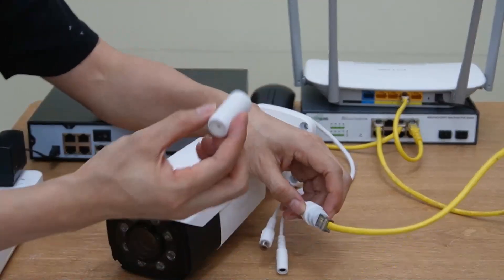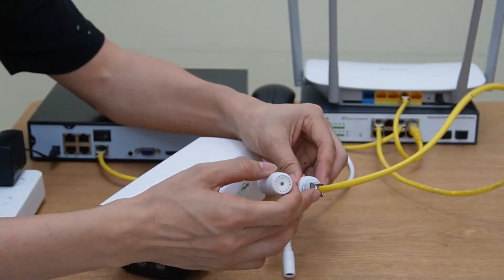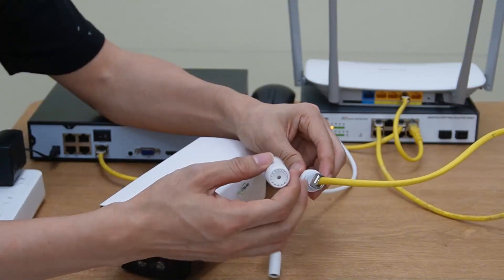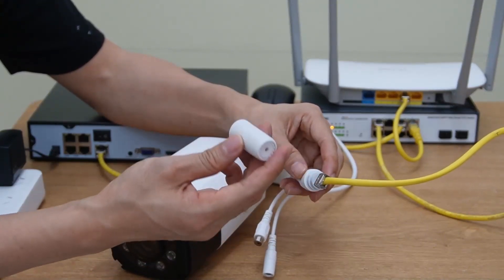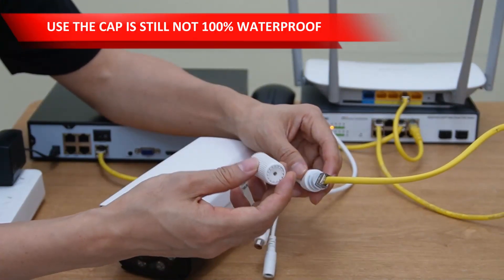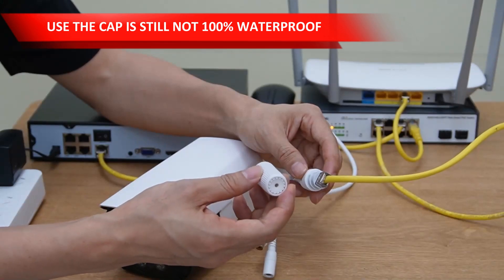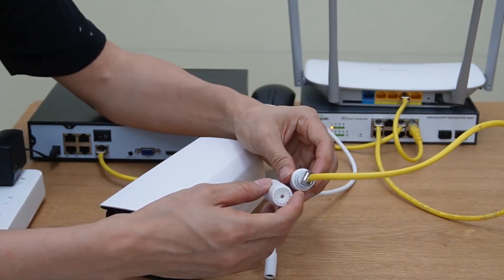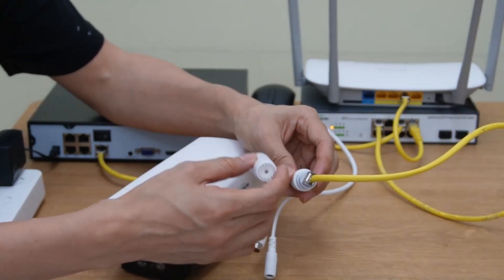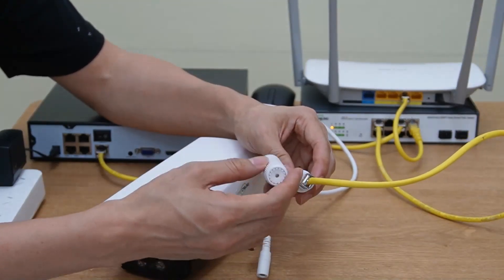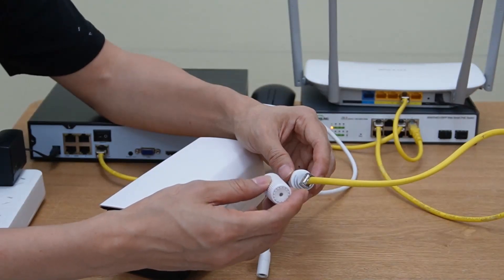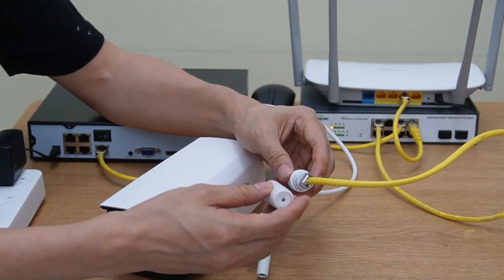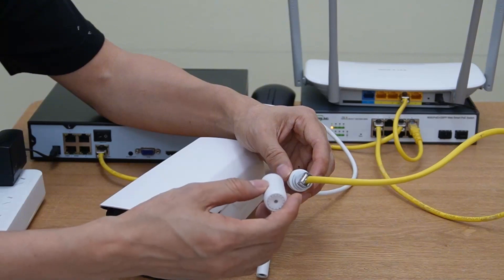The cable supports pass through this cap before we use this connector. One thing I want to point out is, even if we are using this cap, it's still not 100% waterproof. Since the pressure is not strong enough to stop the water entering into this connector. So it's always better to provide extra protection, such as the tube, even if you are using this cap.